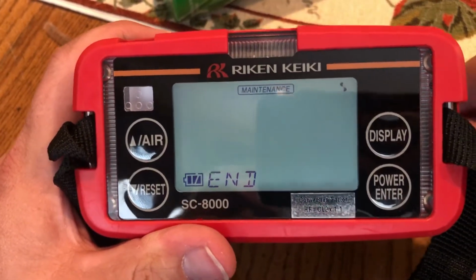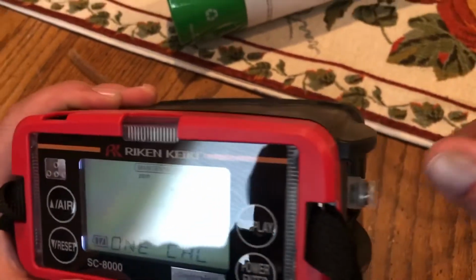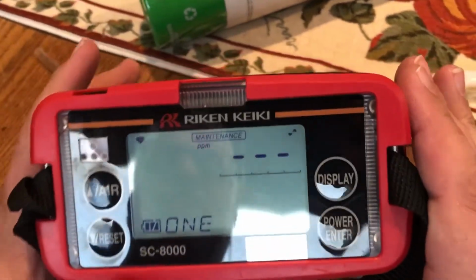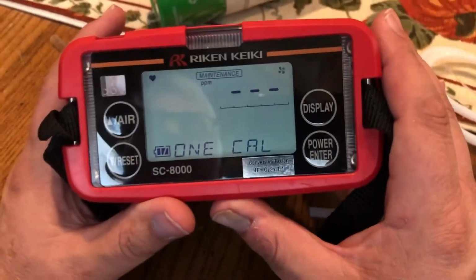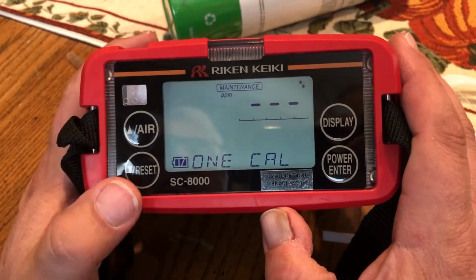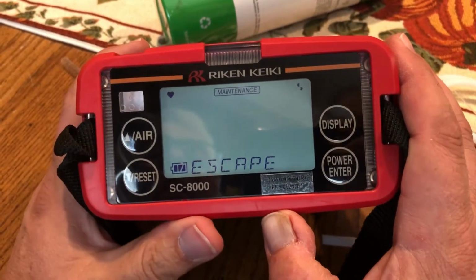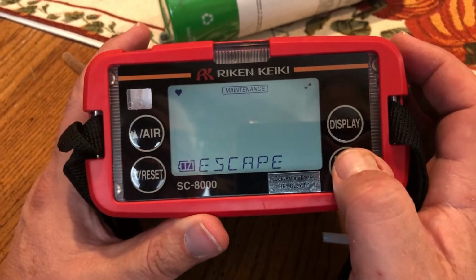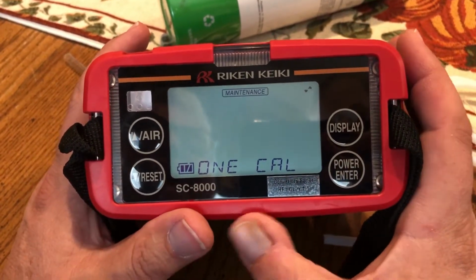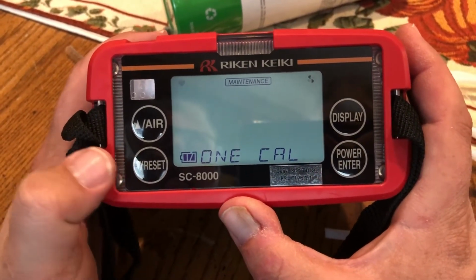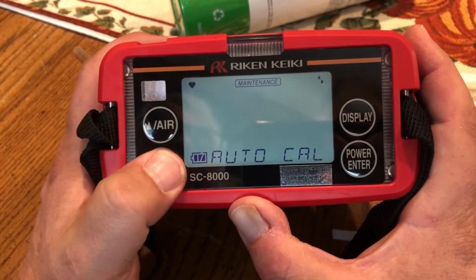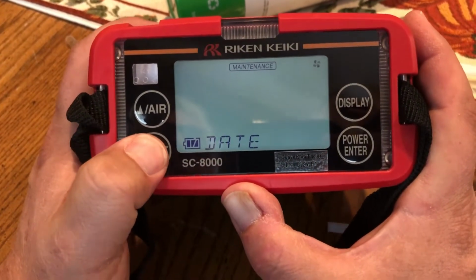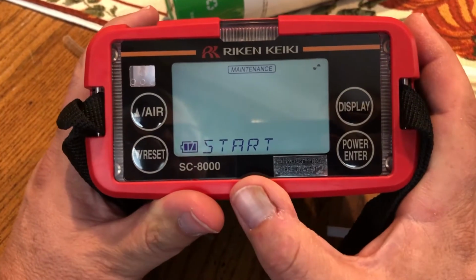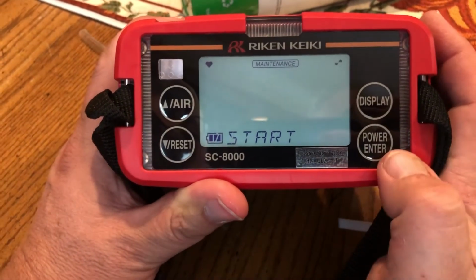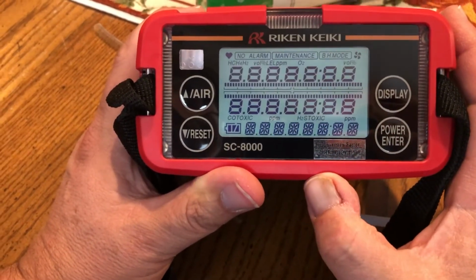It ends. You take off your cal gas and you go back to the 1 cal maintenance menu item. From here, you can hit your down arrow key. It will say escape. You hit enter, and we're back at the 1 cal again. Now we can use that down arrow key to go to the start function. From here, we will be exiting the maintenance menu back into normal operation.